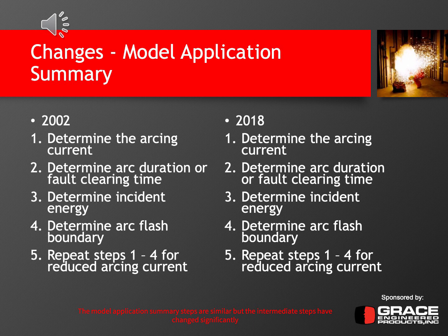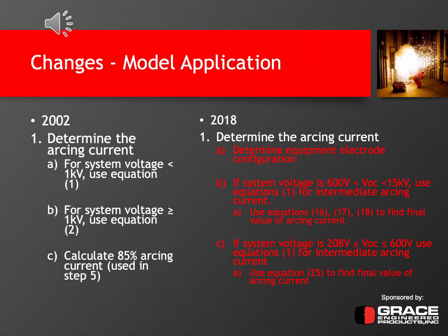Once you know that, you recycle it back into steps 2, 3, and 4 because you would have that minimum arcing current. So in general, from 2002 to 2018, the outcomes of each of these steps are pretty much the same, but the process in determining those outcomes has changed. Diving into items 1 through 5 in a little more detail, you can really start to see the differences between the 2 editions. I haven't put very many equations on here, really none except on a few slides, mainly because the equations are pretty long and would extend this presentation significantly. But all the equations are in the standard, and it tells you step by step what to do. It's a great way to follow, and there's a summary in the standard that tells you how to calculate and determine the incident energy.